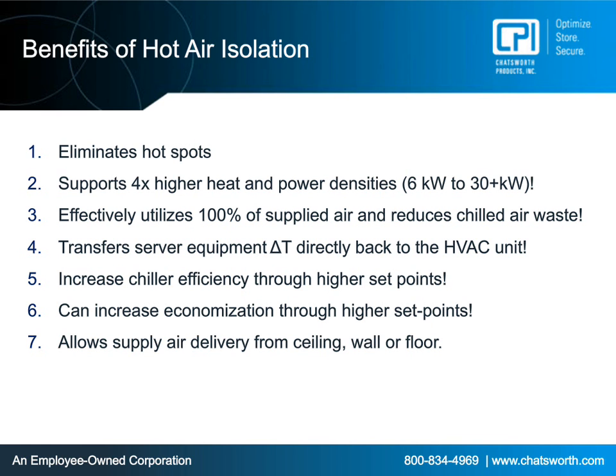The other thing that's going to happen is, with those higher set points, we can take advantage and do some economization. So we can try to shut our HVAC off and use outside cooling or seasonal cooling to help cool our data center.